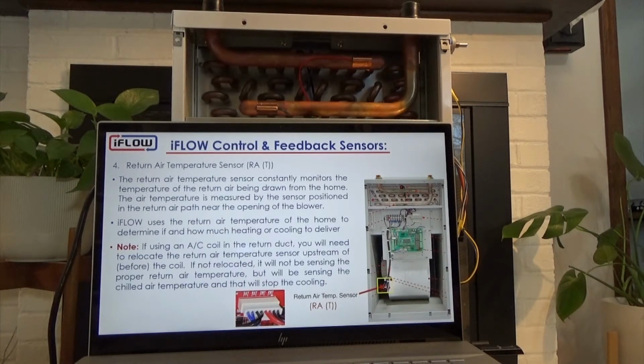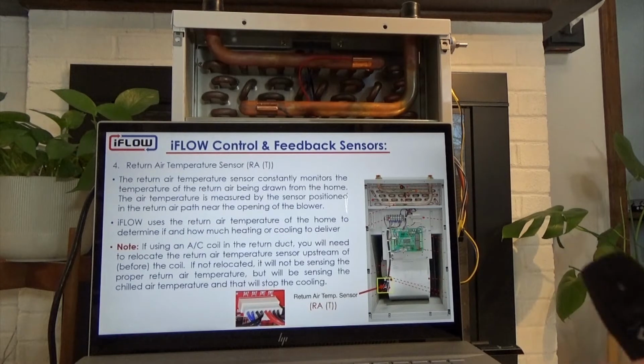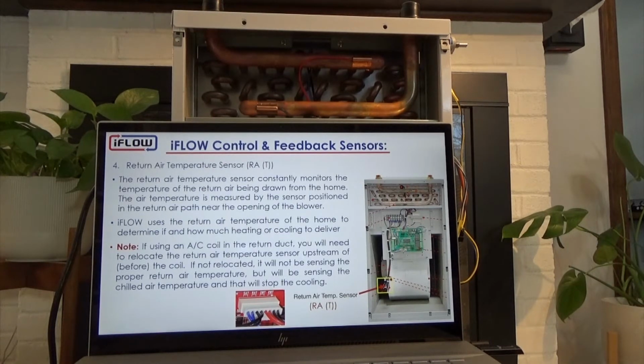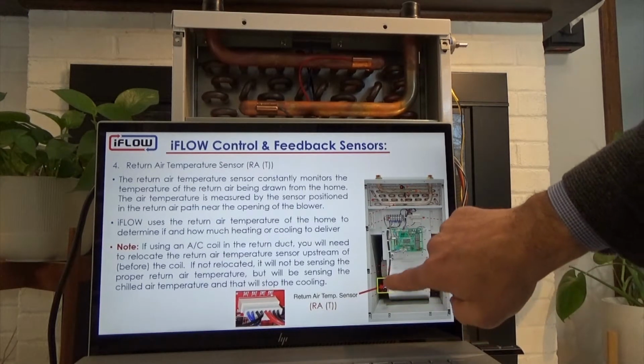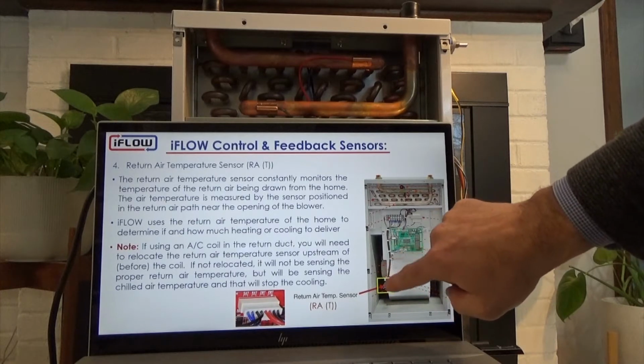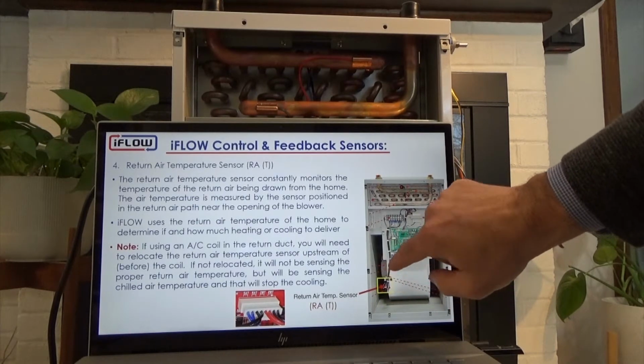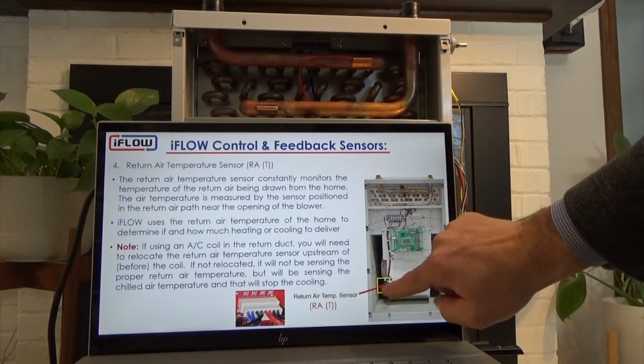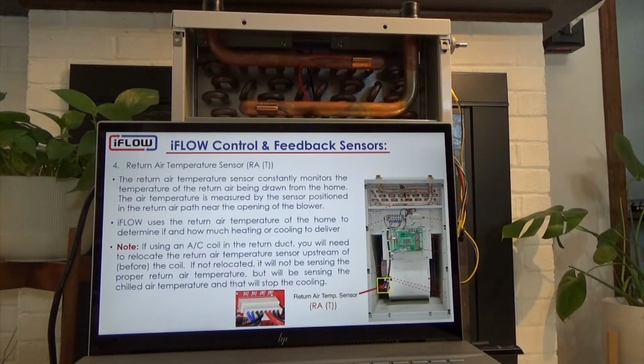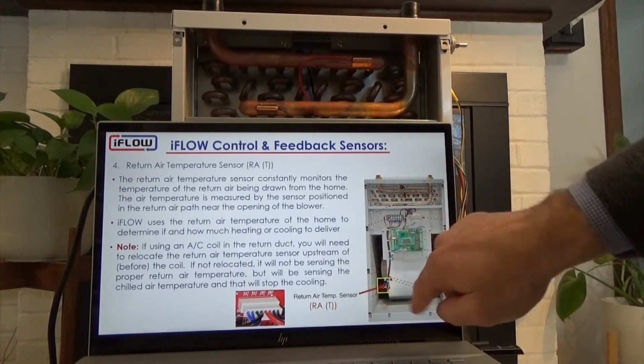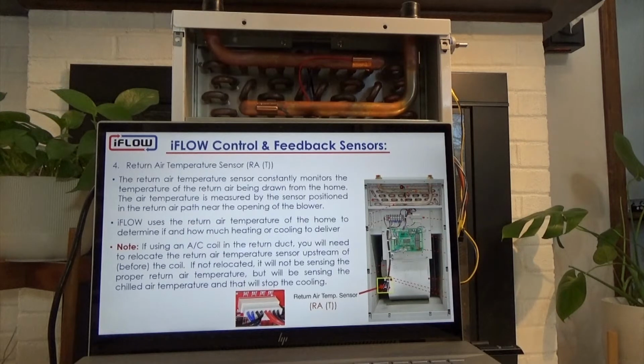The return air sensor is actually located next to the blower, in this lower area, just to the left of the blower as you're looking at it from the front, in the harness that's coming down from the board, all wired together. And it is looking at the return air temperature and deciding how much heating or cooling needs to be delivered into the space.